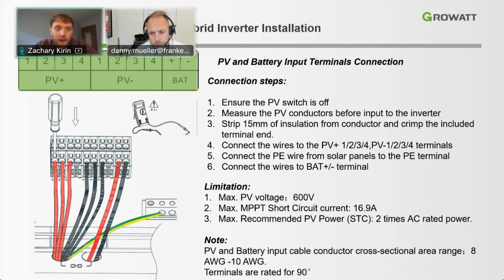I've seen installations where they do not use the terminal ends. This has not been a problem in the past. I recommend utilizing what comes with the inverter though. Connect the wires then from PV plus and PV minus 1, 2, 3, and 4. This would be an 11.4 kilowatt system, so it comes with 4 maximum power point trackers. There will be a reduction based on the type of system you have, based on the power class, but this particular one is a 4 maximum power point tracker installation.